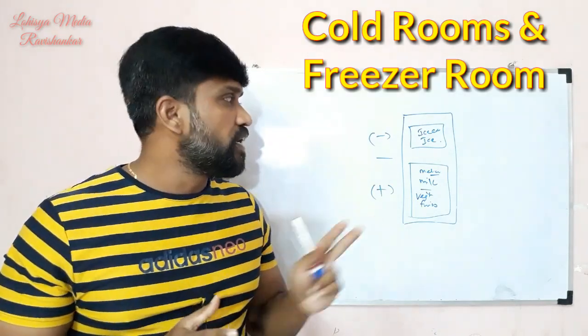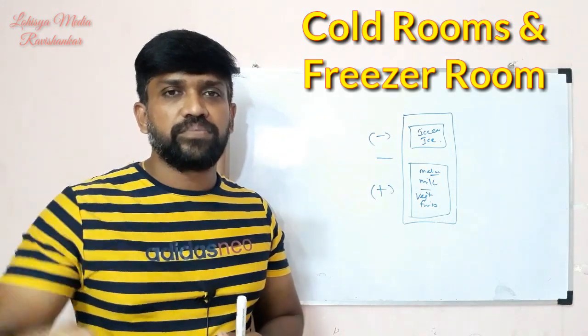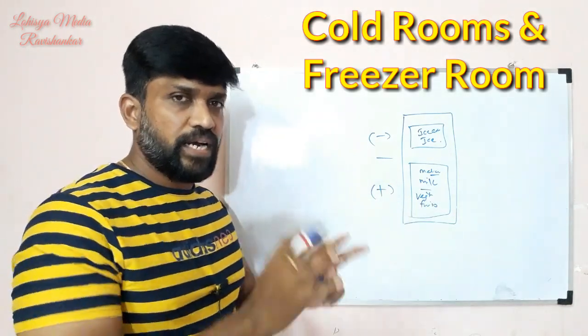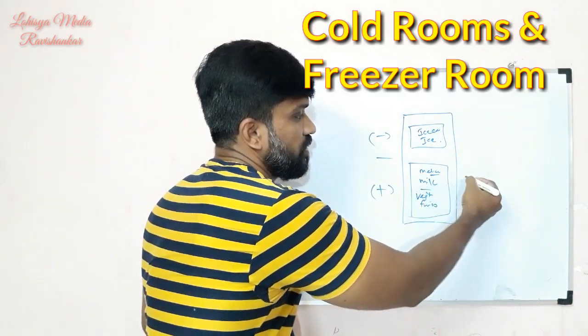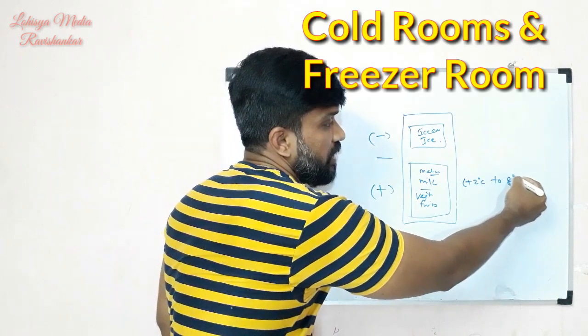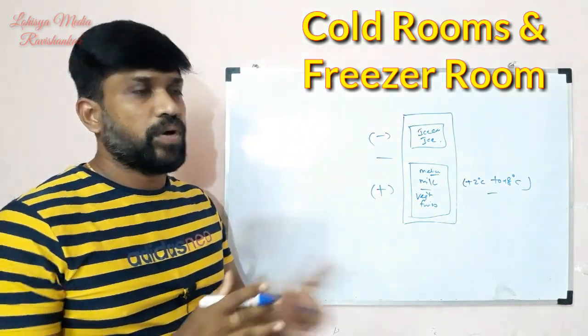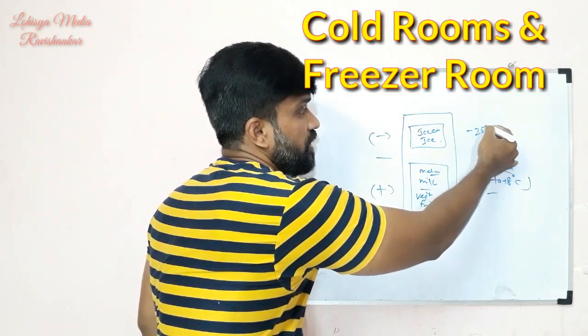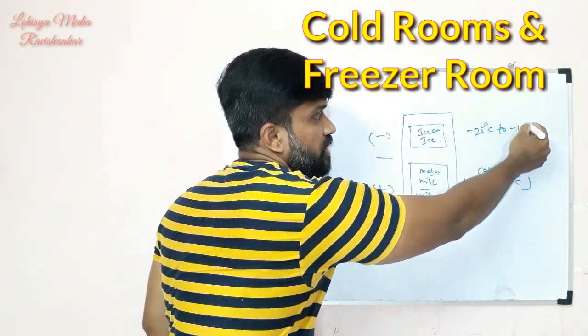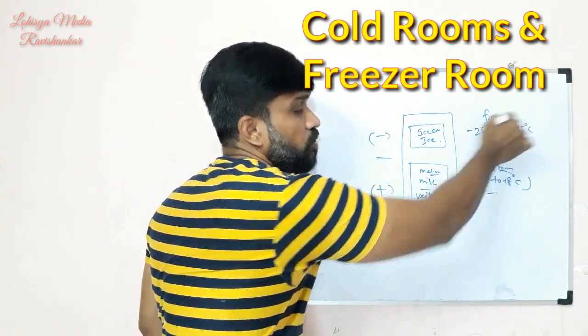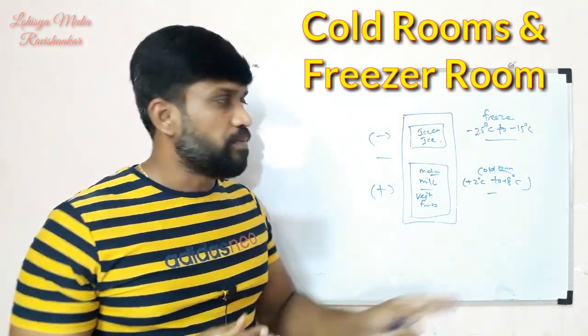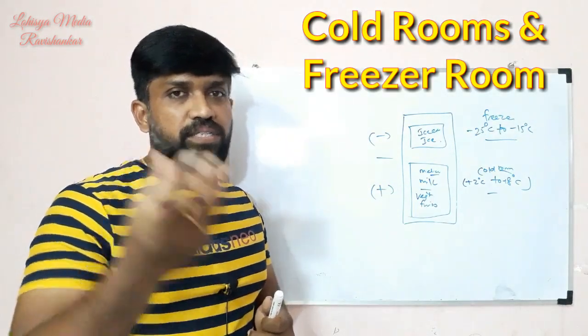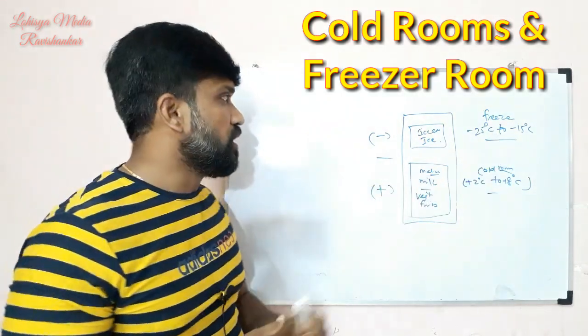WHO has standards and rules for cold rooms and freezer rooms regarding temperature. Freezer rooms are maintained at minus 25 degrees Celsius to minus 15 degrees Celsius. Cold rooms are at positive temperatures — around plus 2 degrees Celsius to plus 8 degrees Celsius. In the freezer, the temperature will be at or below 0 degrees Celsius, which means products will automatically freeze.